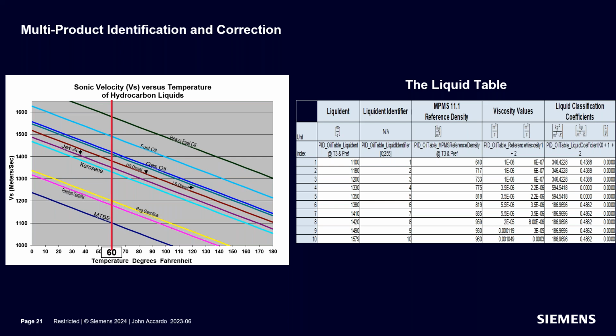Now, without Lamb wave, and without that wide beam, it might not be so easy to do this, because each time one of these products changes, the refraction angle of the sonic beam changes. And if your transducers weren't well matched to the pipe, your wave shape would change. And so you could have a meter that was accurately measuring flow for one liquid, and then you switch to a different liquid and suddenly your accuracy is not so good anymore. And that's because your wave shape changed. So it really, Lamb wave, and of course Snell's law going back to 1621, all play heavily into being able to do this kind of work.